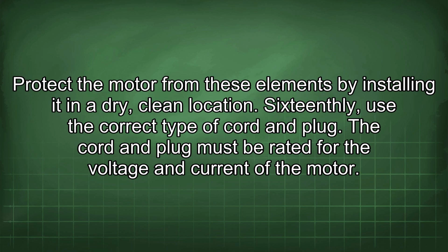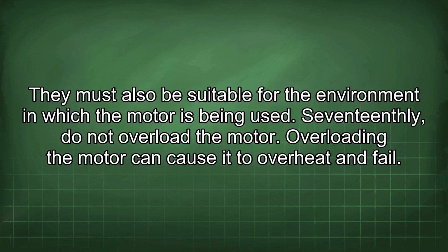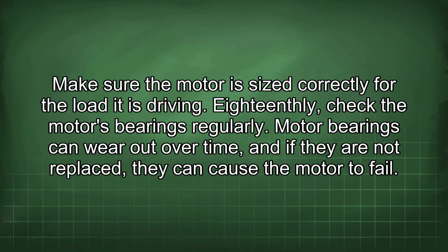16thly, use the correct type of cord and plug. The cord and plug must be rated for the voltage and current of the motor. They must also be suitable for the environment in which the motor is being used. 17thly, do not overload the motor. Overloading the motor can cause it to overheat and fail. Make sure the motor is sized correctly for the load it is driving.